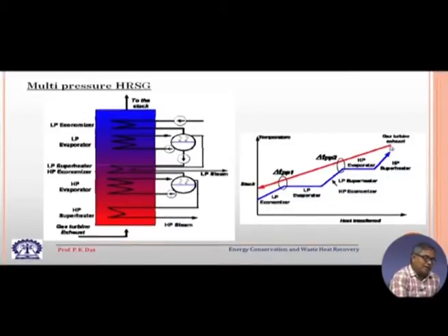So, more or less you see we are following some sort of a parallel line. Of course, this kind of nature cannot be avoided as there is steam generation, I have already explained. But compared to the single pressure operation, by providing two pressures, these two curves are coming close to some parallel curves. So, this is the achievement we get by producing two pressures.